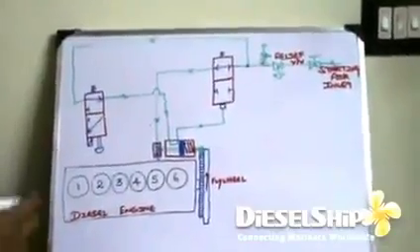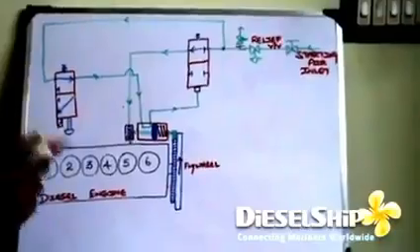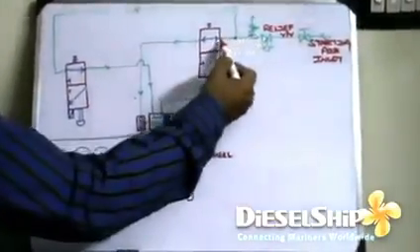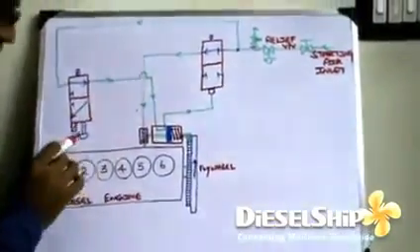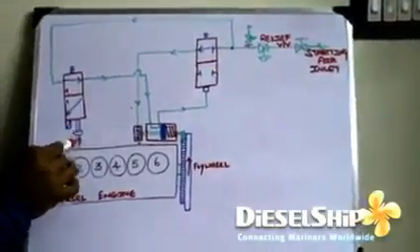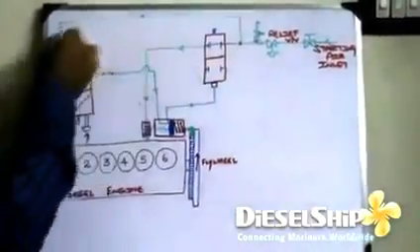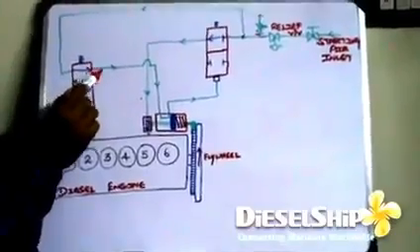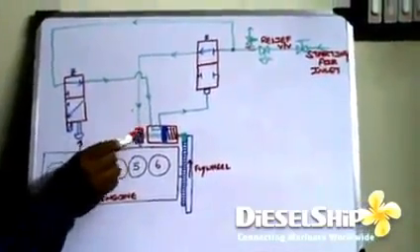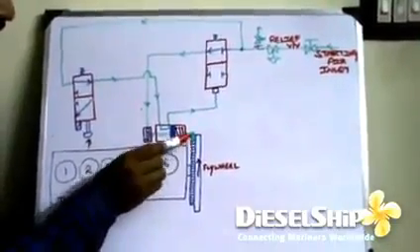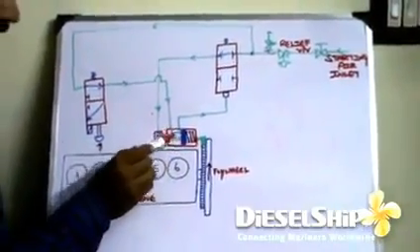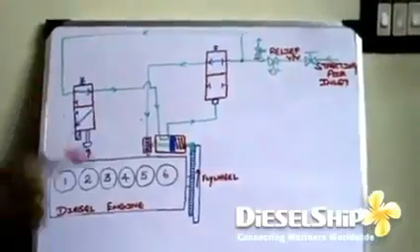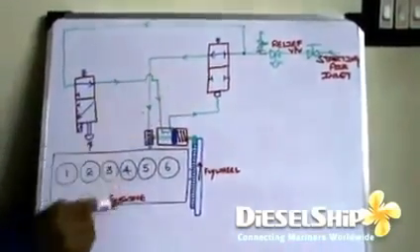So this circuit over here represents the air motor when it's working. So as I said earlier, the 30 bar air comes over here, and I start the engine manually by pressing this lever, and the 30 bar air which is available waiting over here - so as the valve gets shifted, it passes through the control valve and then it passes through. Thus immediately it pushes the piston down. Thus the pinion engages with the flywheel, and as it pushes, it passes out and then operates this control valve pneumatically. So the compressed air operates this control valve.